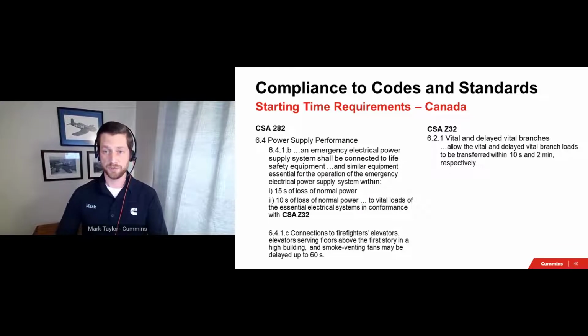Other loads, such as those crucial for firefighting or healthcare delayed vital loads, may be on a 1 or 2 minute requirement. The important note here is that these requirements do not exceed those by NFPA 110 type 10 for emergency power supply systems. And once again, these are performance requirements that are not specifying any fuel source.